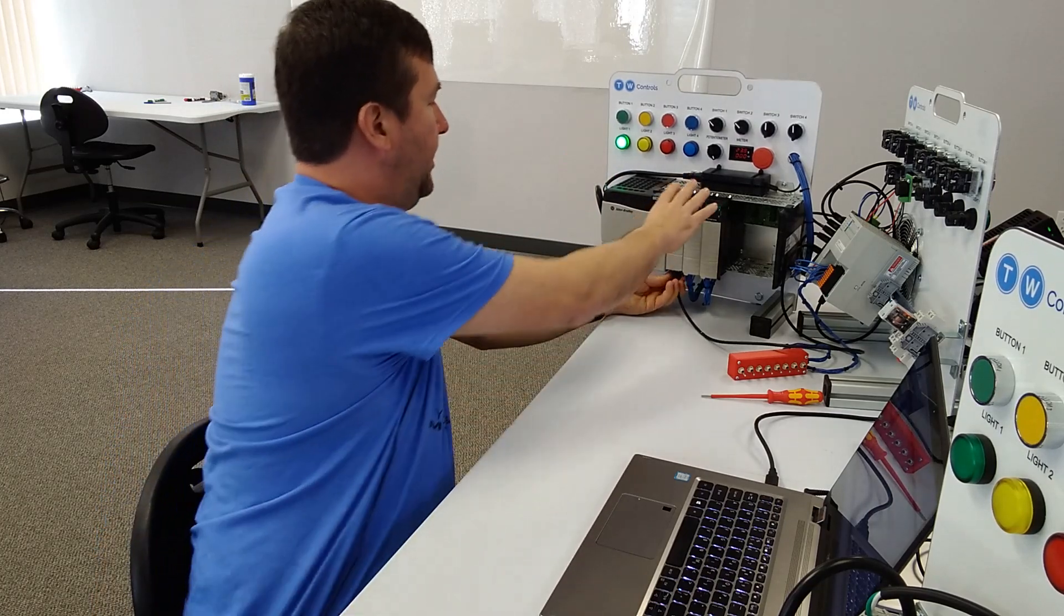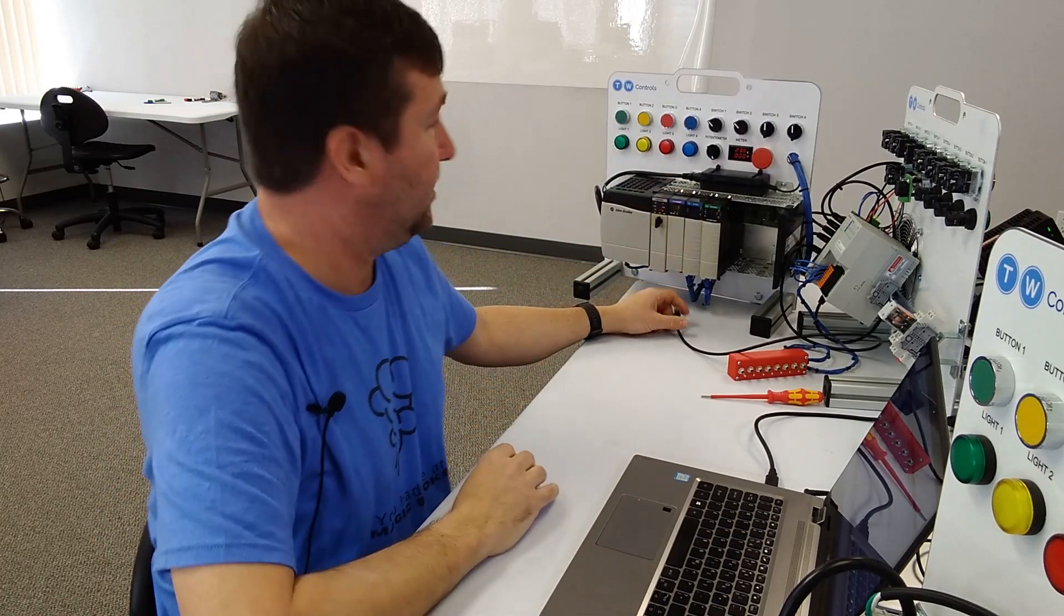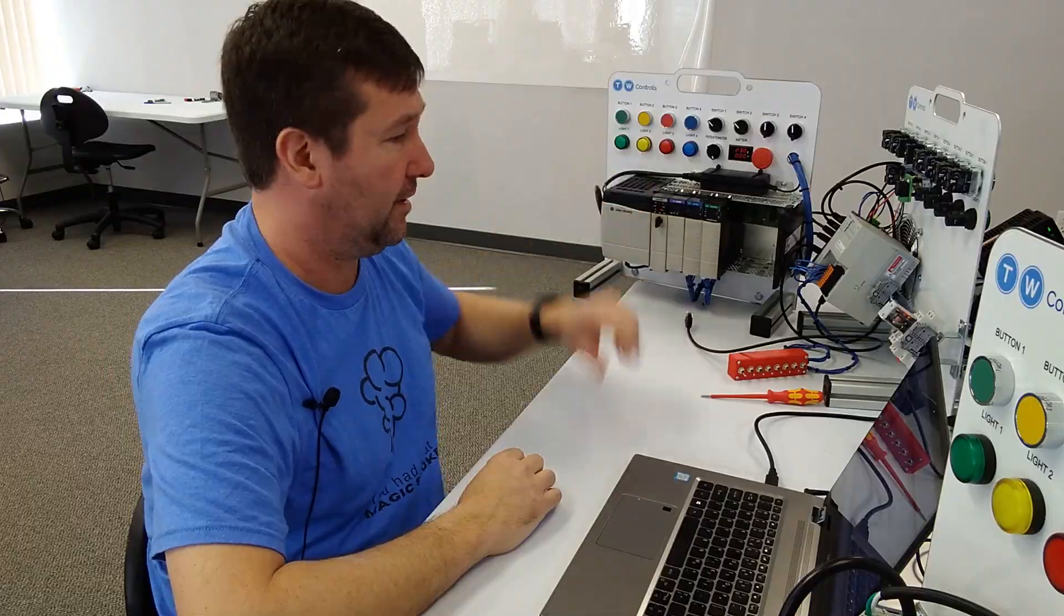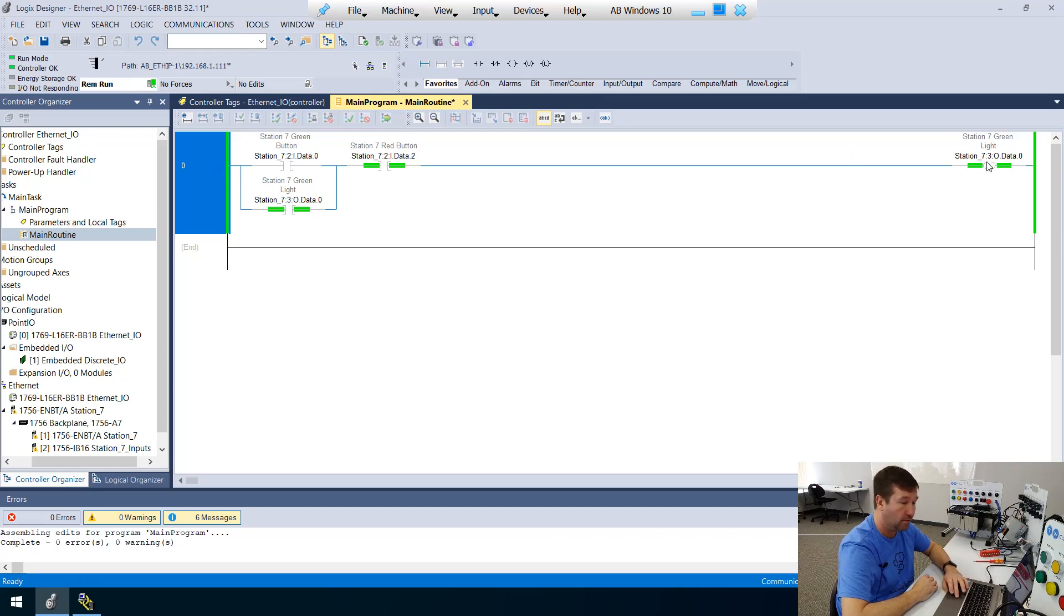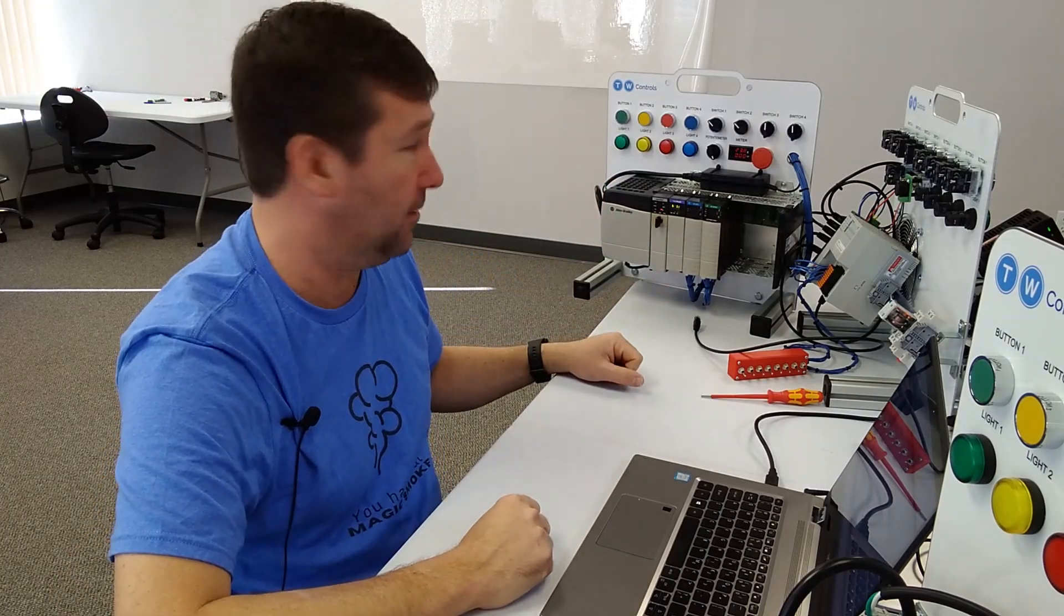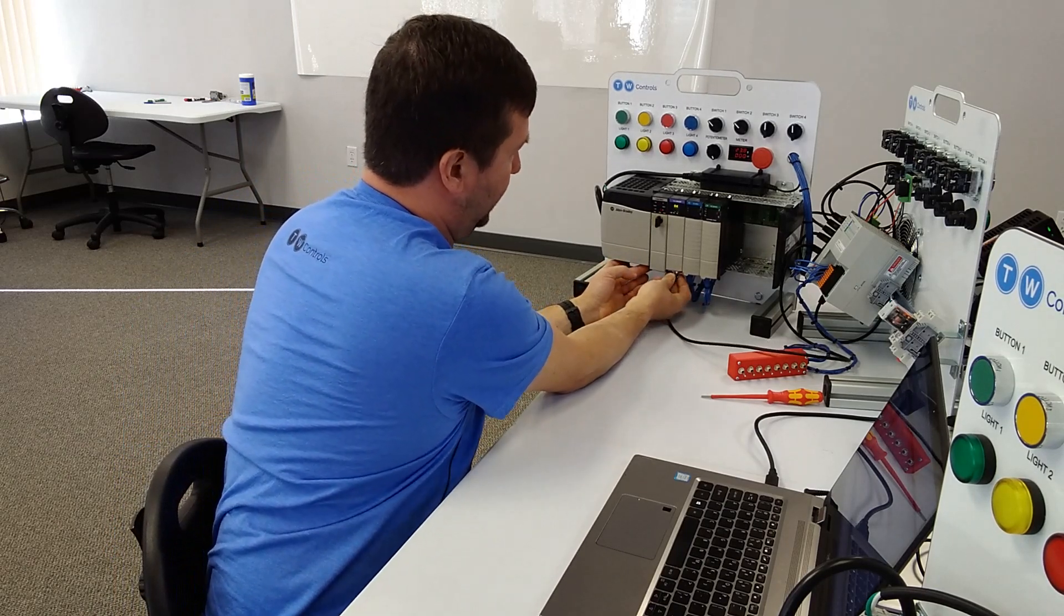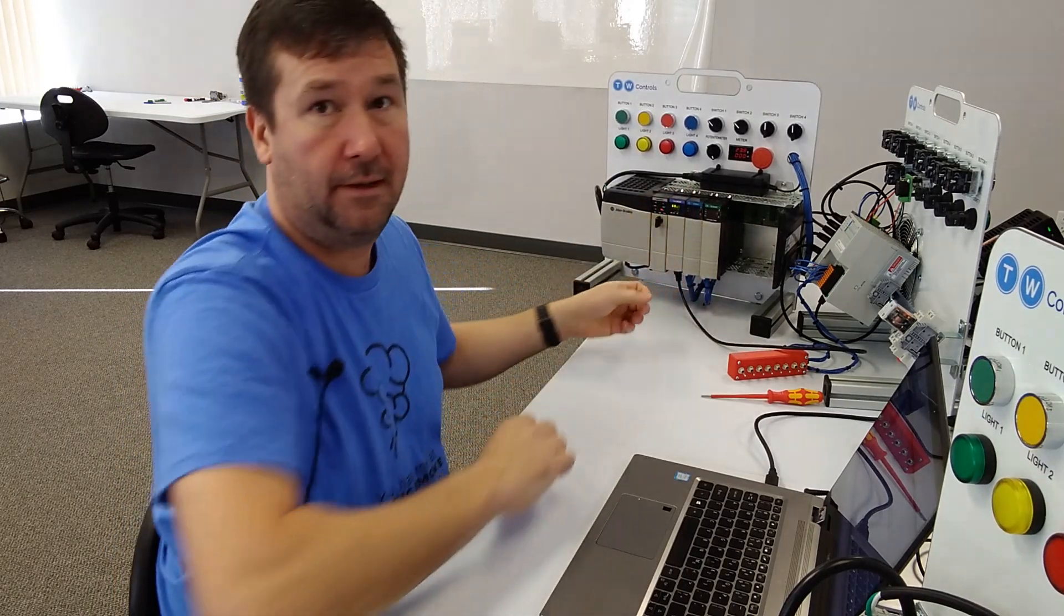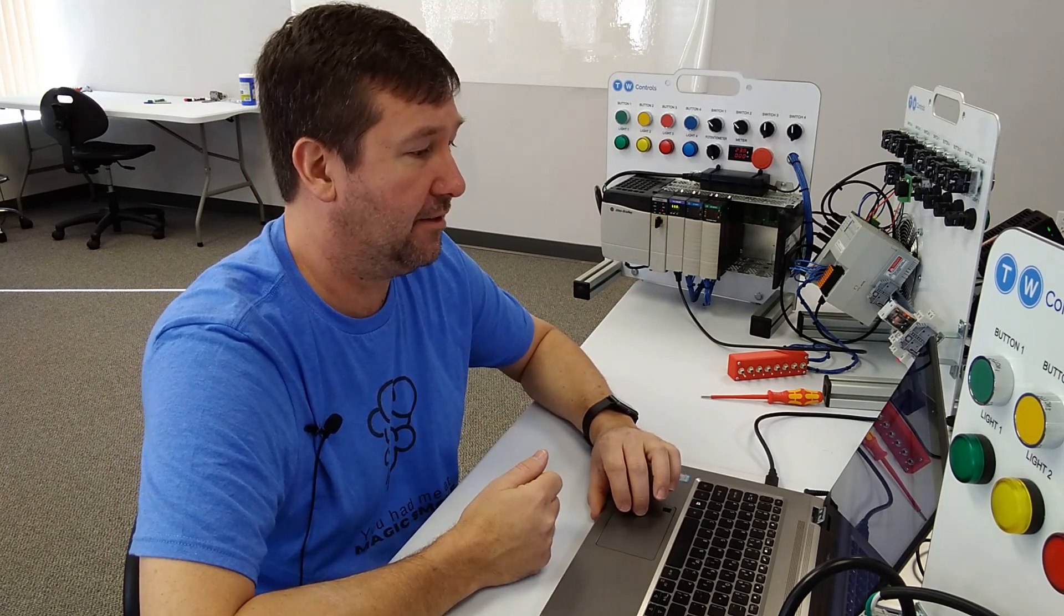And then I unplug our ENBT, the green light is going to immediately go out and our IO now is not responding. Now, notice, though, in our program, the green light is still on, even though I can't communicate with it. So now I'm going to plug it back in.